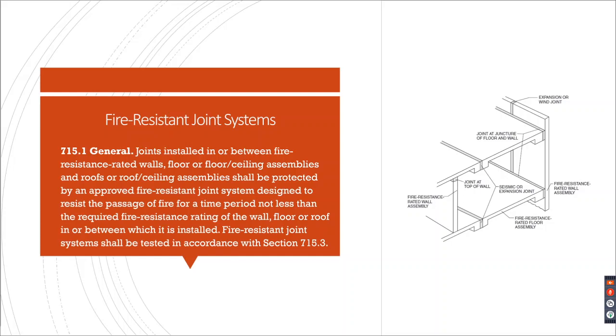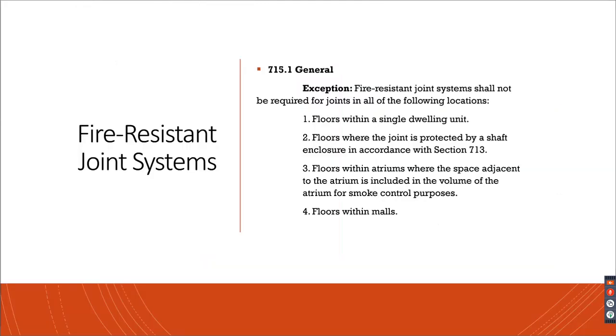Again, remember that when they're at the horizontal portion, they're still part of that smoke compartment, and you still are looking at an L rating. So a lot of times you will need an engineering judgment to get that L rating in some of these. Some of them actually exist.